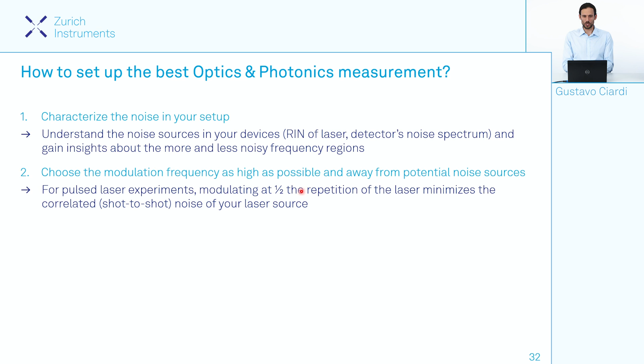Then, once we've detected our signal, we need to select the best measurement approach based on the characteristics of that signal: low duty cycle, high duty cycle. And this is sometimes hard to do a priori. The only real way to understand which is the best measurement approach is by comparing the signal-to-noise ratios of the different approaches, for example lock-in amplifiers and Boxcar averagers. In this way, once we know which one leads to the best signal-to-noise ratio, we can make an informed choice.